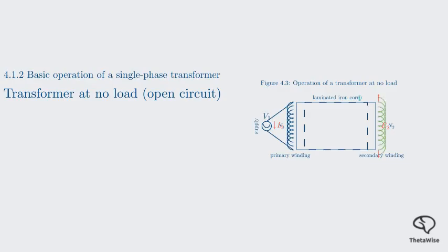We'll begin with a transformer operating at no load, also known as an open circuit. In this state, as shown in Figure 4.3, an alternating voltage V1 is applied to the primary winding. Notice there is no load connected to the secondary side. This alternating voltage causes a small current called the no-load current I0 to flow through the primary winding. This no-load current has two main components. One component creates the magnetic flux, and the other supplies the losses in the core, like eddy current and hysteresis losses. The no-load current I0 produces an alternating magnetic flux, represented by phi, in the primary winding. The laminated iron core is designed to channel this magnetic flux. The flux path is almost entirely contained within the core, and it passes through both the primary and secondary windings.